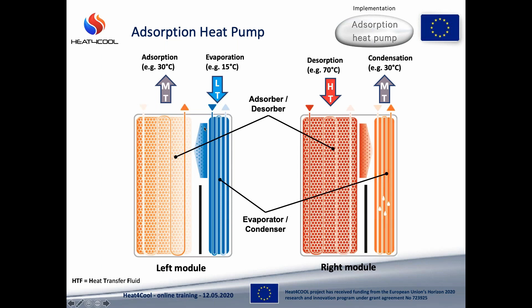In the adsorption-evaporation phase: during adsorption, heat is released to the ambient, therefore we need HTF at medium temperature level (MT) circulating through the adsorber, cooling it down. On the other hand, the evaporation process collects heat from the HTF — that's our cooling effect — and HTF at low temperature (LT) circulates through the evaporator. In the desorption-condensation phase, we have to add heat to the sorbent to regenerate it, so HTF at high temperature (HT) flows through the desorber, warming it up. During condensation, similarly to adsorption, heat is released and has to be dissipated, and here we use HTF at medium temperature (MT) again.